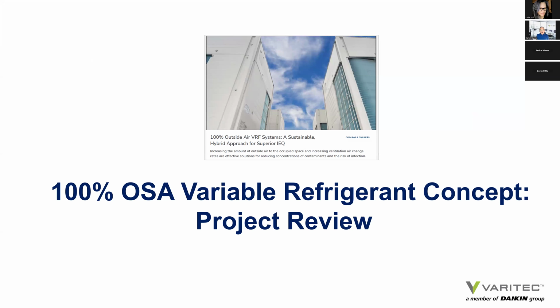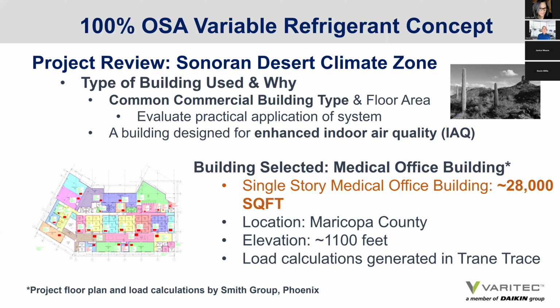So, what is the 100% outside air variable refrigerant concept? A project review. Well, to do this, I worked with my friends at Smith Group, Eric Martin and Steven Zag, and we wanted to look at VRV for small to medium-sized buildings. We so often associate high-performance buildings with large institutional structures, 100,000 square feet, 150,000 square feet. But what about the small and mid-sized buildings? What type of advantage would a 100% outside air variable refrigerant system offer to smaller building owners?